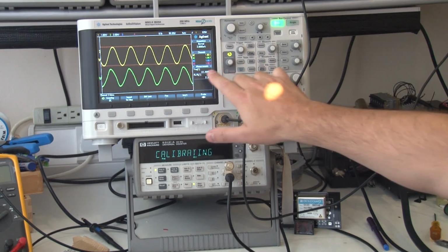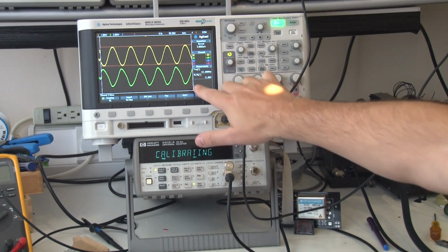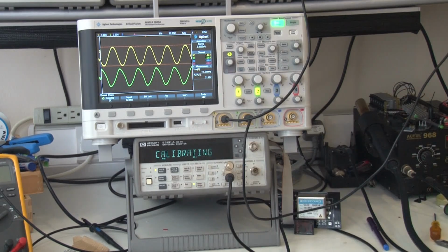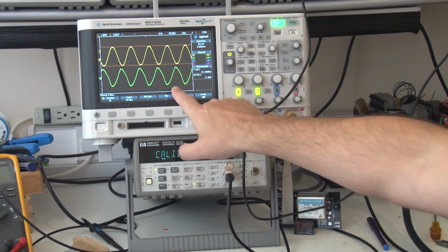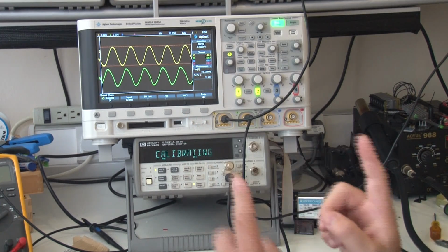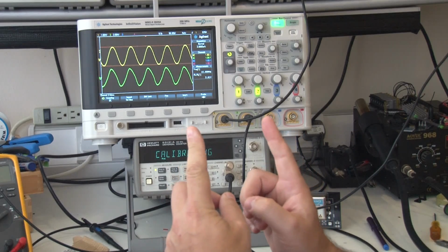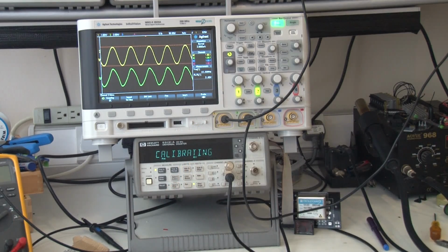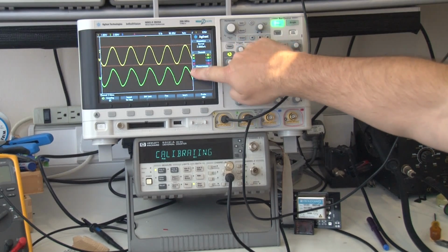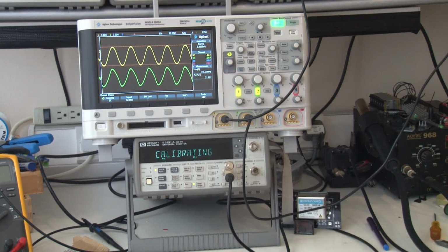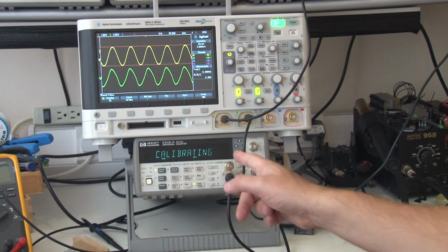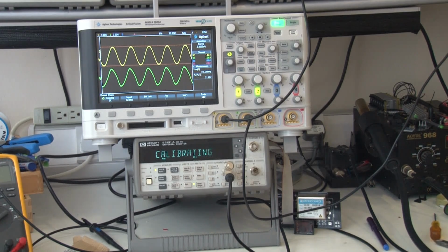Once it finds its window, it'll probably go the other way a little bit, and then it should bring itself back in. Actually, it's done a pretty good job at finding that. So it's gone in the other direction now. It's found its window, and now what it's going to do is slowly trim to a known calibration point. It looks like I've done this a few times now. That looks like a pretty good calibration cycle. You can see that the two are locked. It's just playing around there. Maybe it's running just a little bit slow, but yeah, that looks like a good calibration cycle. This should complete in a second, and then we can see what the results are.